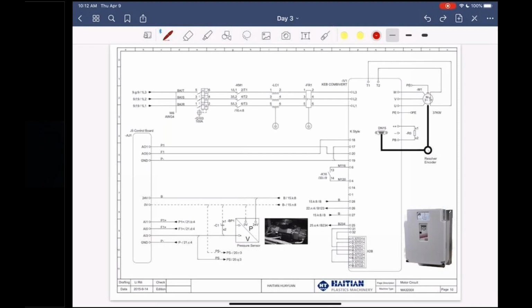What also happens inside this KEB drive is it also converts the frequency. It raises the frequency and allows the drive to send out a certain frequency. I believe it's 0 to 1000 hertz. And that frequency is what actually makes the motor, the servo motor, rotate. Any questions on this? Okay.